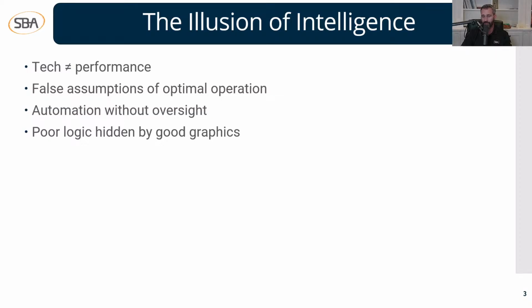Faulty logic or default settings are often never corrected. During startup and checkout, maybe something was never corrected in the software—like a low limit that wasn't tested, so you never knew if it would protect your coil or not. A lot of user interfaces and startup software come with default settings, and if those are never corrected, you want to make sure they're backed up by whatever's in the plans and specifications—unoccupied set points, occupied set points, time of day schedules. Make sure they're not just left on default, but customized and set up the way the job was designed.